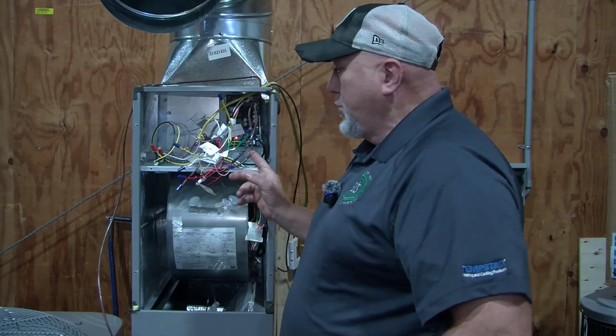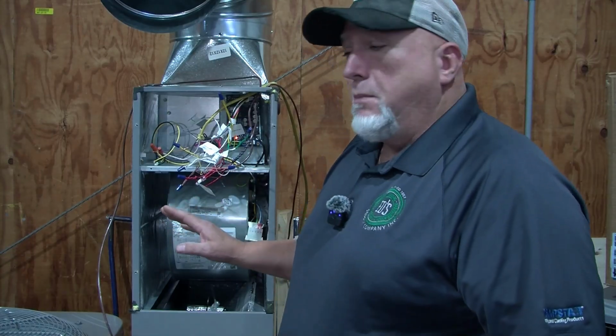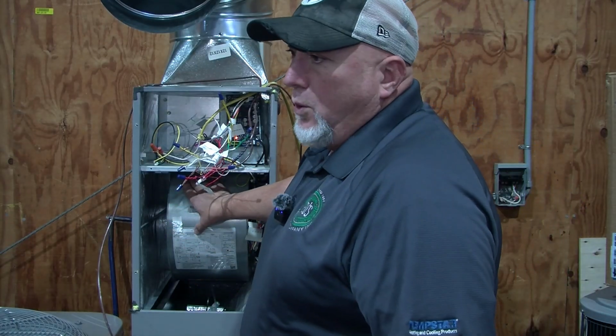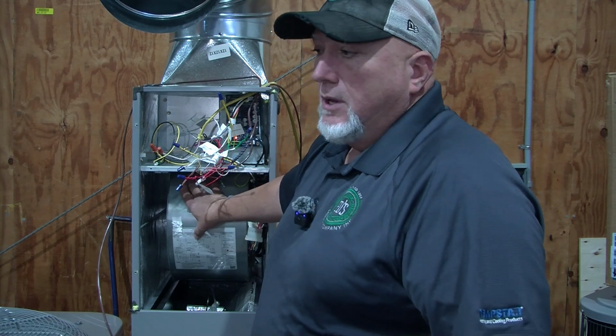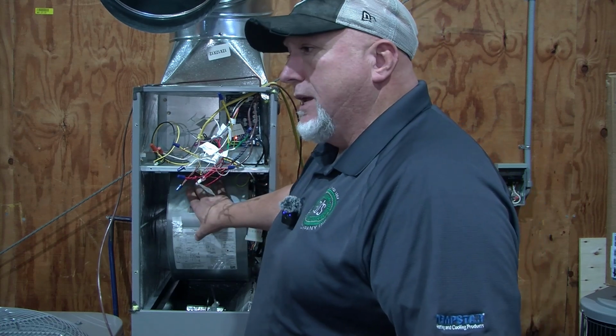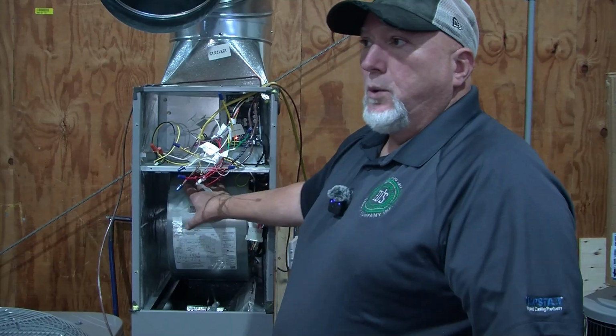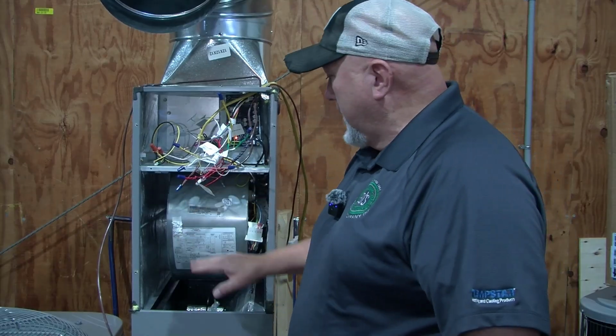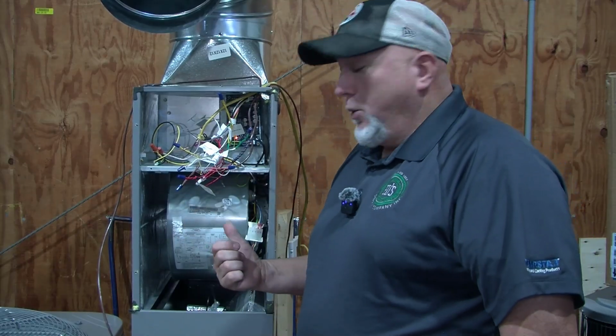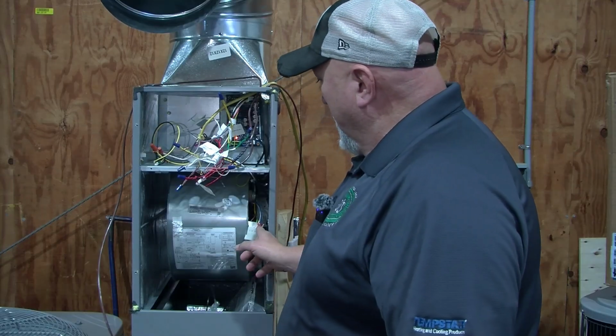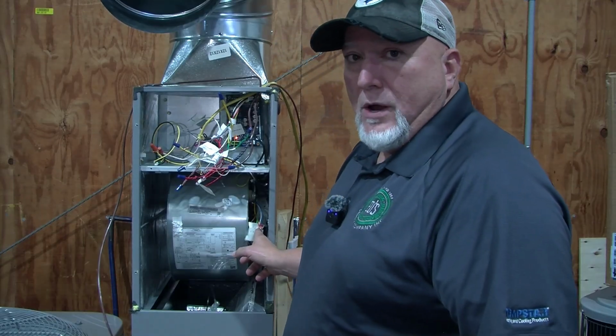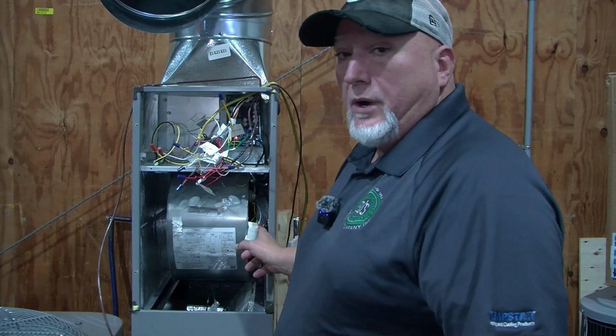These new 454B units and this new control board, these motors are wired up with their 208, 230 at all times, and the 24 volt is your switch. So when it sees 24 volts, it's going to come on. Now we're in cool mode on this, so we're going to have 24 volts power coming on this blue wire. If we were in heat, power would be coming on the white wire.